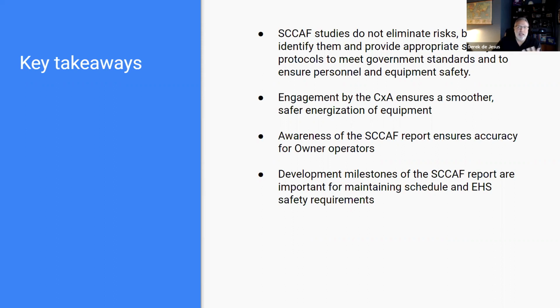As CxAs, you should engage to ensure a smoother and safer energization of equipment. What does that mean? During construction, contractors are always pressing to energize equipment so they can continue to move the project forward. They want to energize a panel, a transformer, mechanical equipment, so they can move on. But realistically, they need to make sure they have the SCCAF report developed and applied before they do those steps. Awareness of what the SCCAF report does and provides is in everybody's best interest, including the owner operator of this facility. It ensures safety all the way down to the installing trades during a construction project.